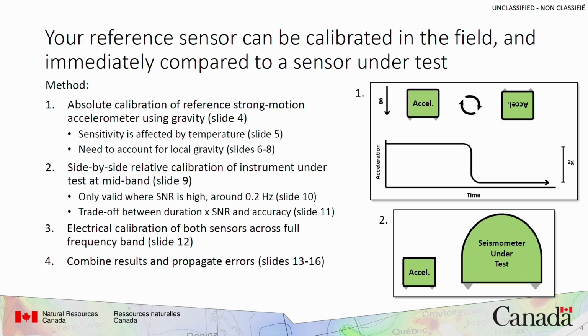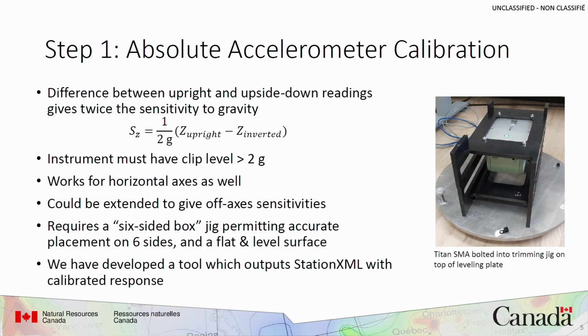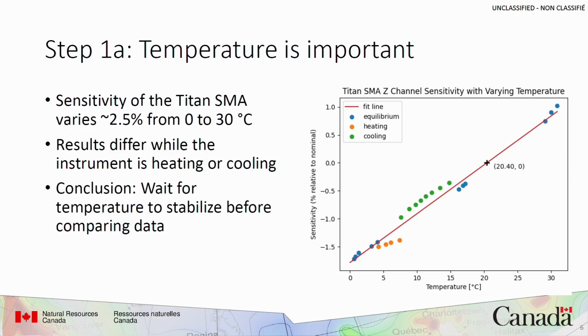So the method consists of 4 steps. First, we do an absolute calibration in the field of an accelerograph using gravity. This actually just takes a few minutes. Second, we immediately do a side-by-side calibration with a weak motion seismometer. This can take a few hours or many hours depending on the ambient noise and the desired accuracy. Third, we do an electrical calibration of the accelerometer and seismometer. And fourth is we combine all the results and add up the sources of errors. So most of the slides that follow focus on those first 2 steps.